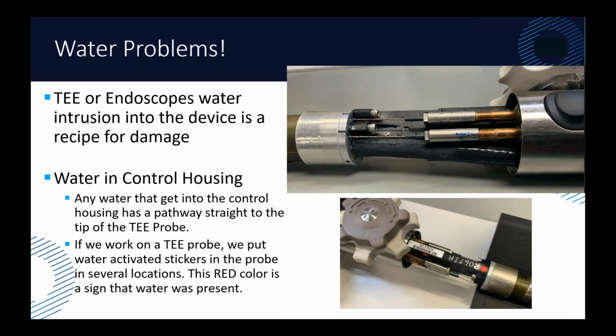You can see here, there's the little wires for the articulation. And then here's another view of the top. You can see there's wires there. These red dots, when a TEE probe goes through our facility, these are actually water activated red dots. So they're not red until actual water touches them, not humidity. It won't go off because of humidity. It actually has to have water touch them.